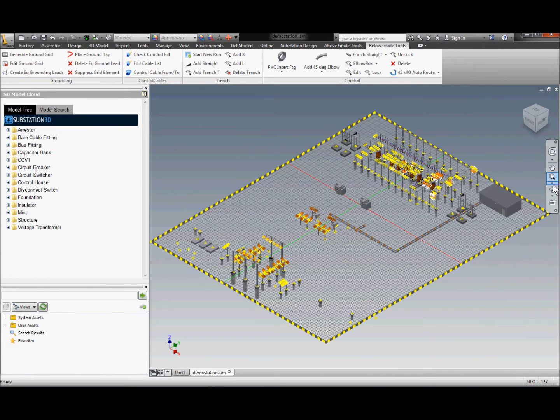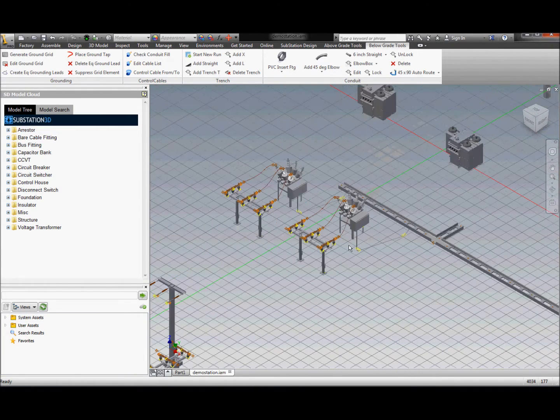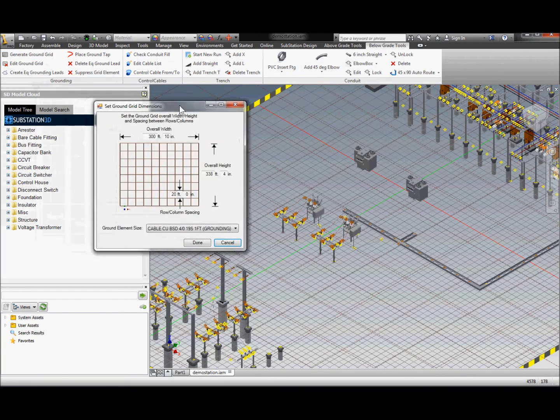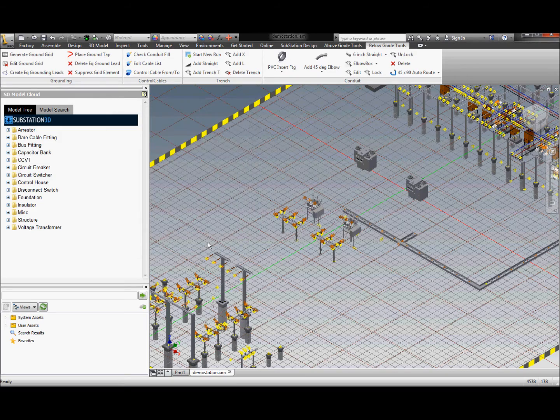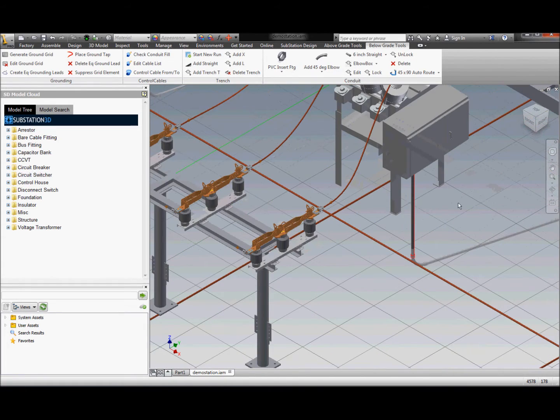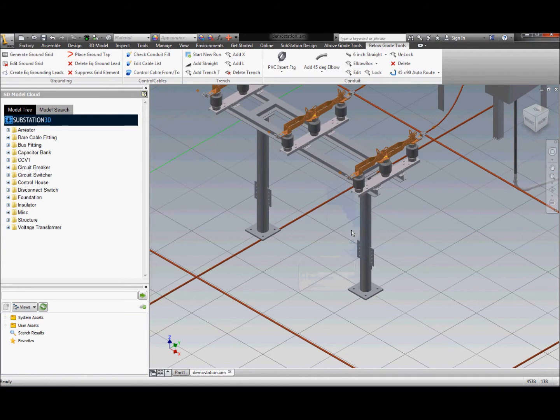We have several grounding tools available as well. Inside the substation design tools, we can generate both a ground grid as well as connect each piece of equipment with grounding rods and lugs. Using the generate ground grid tool, it takes a best-guess estimate at the size of the overall grid and a spacing in between — fill in the numbers, select done, and it generates the grid, showing the rods across the bottom of the station. Let's zoom into the disconnect switch and put in a ground lead from the equipment over to a ground rod. We'll go to our substation menu and create an equal-length ground lead, select a piece of equipment, and it will find the closest location to put a ground lug.